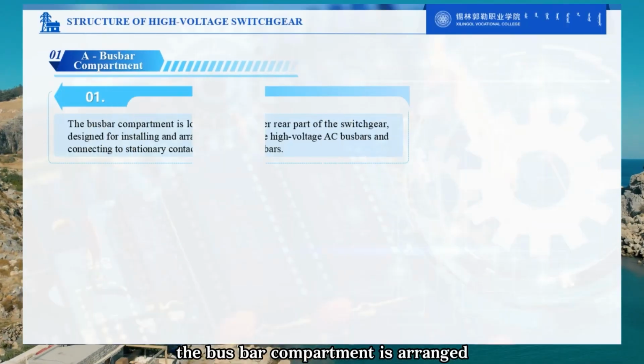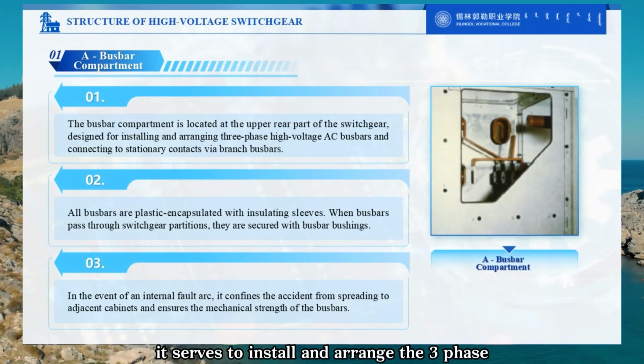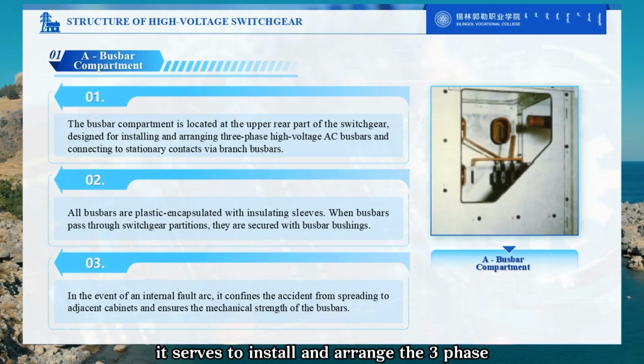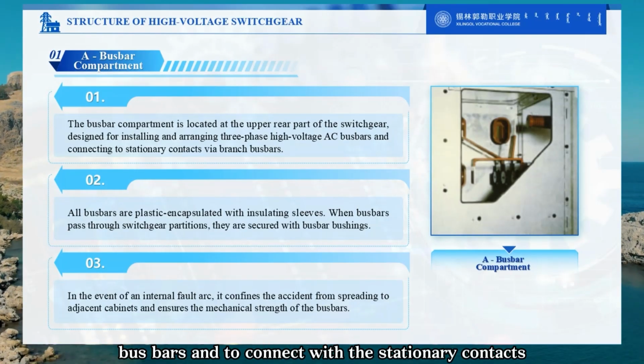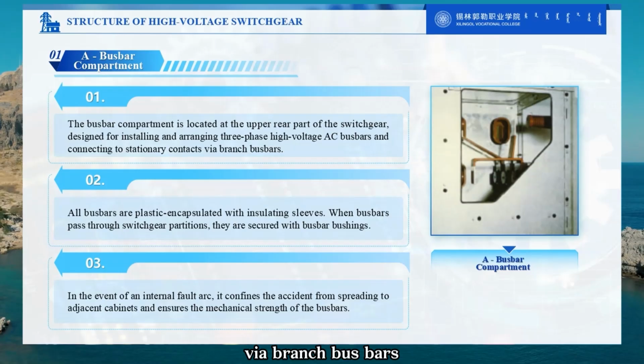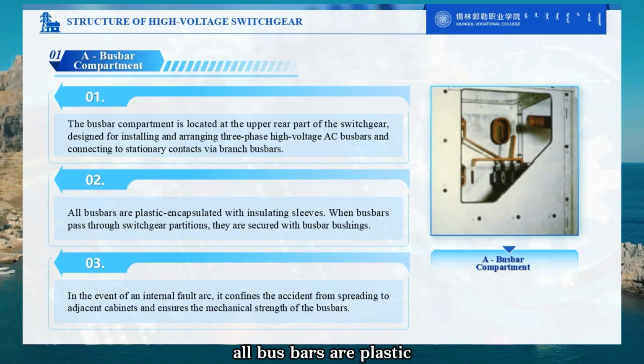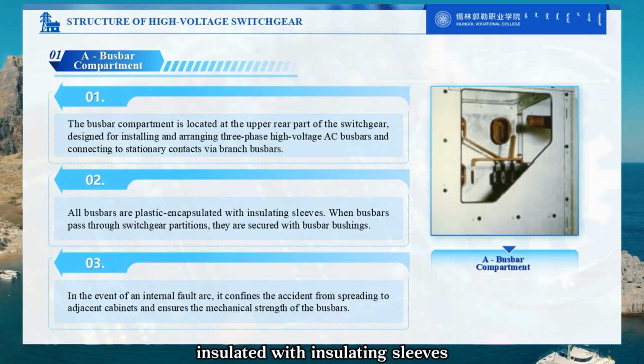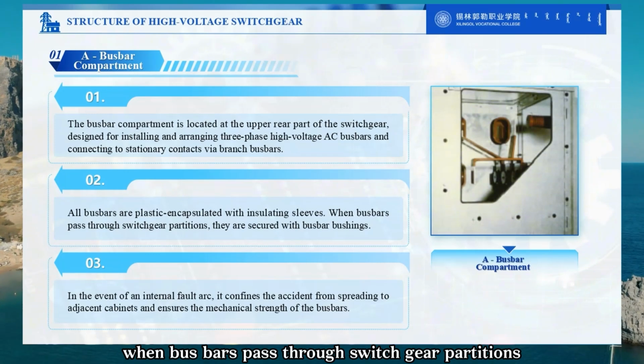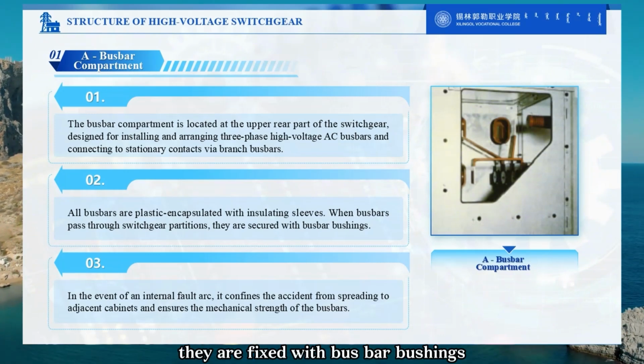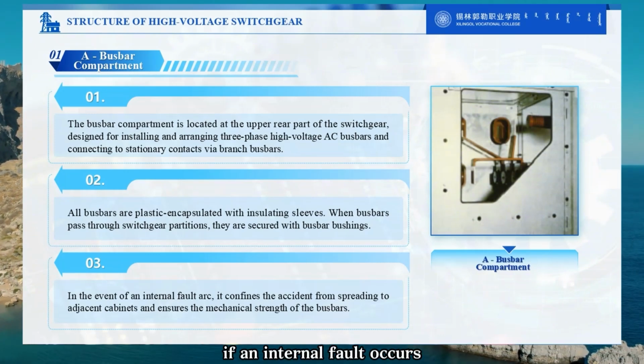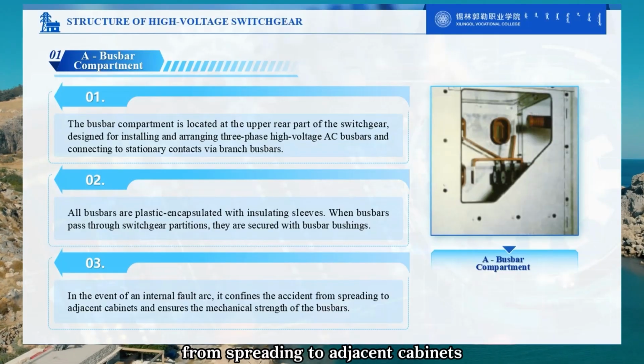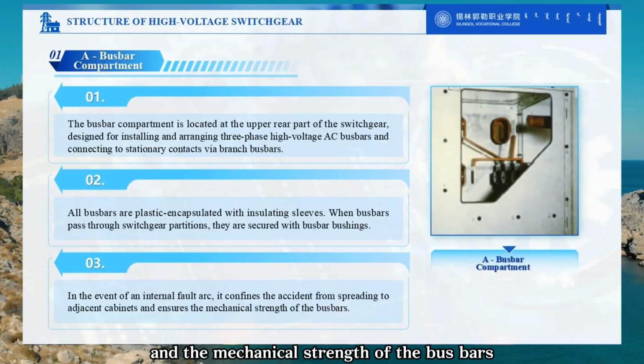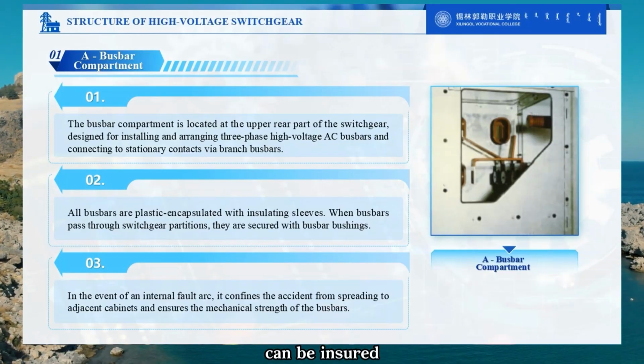The busbar compartment is arranged at the upper rear of the switchgear. It serves to install and arrange the 3-phase high-voltage AC busbars and to connect with the stationary contacts via branch busbars. All busbars are plastic insulated with insulating sleeves. When busbars pass through switchgear partitions, they are fixed with busbar bushings. If an internal fault occurs, the arc can be limited from spreading to adjacent cabinets, and the mechanical strength of the busbars can be ensured.